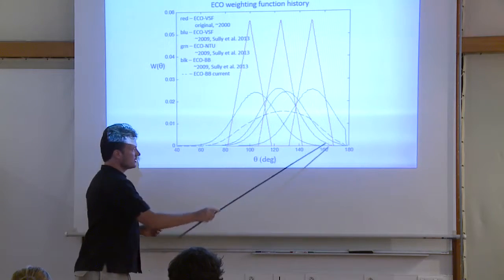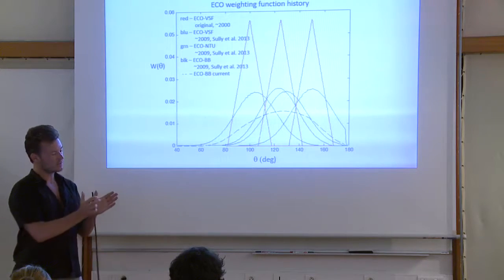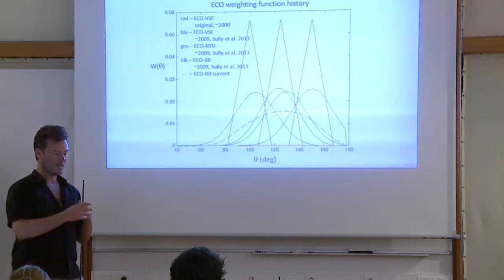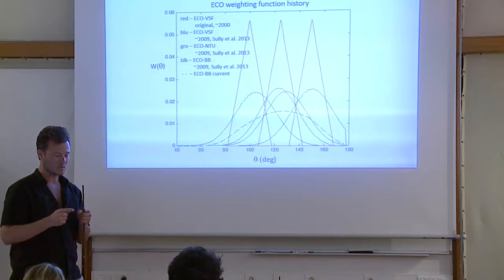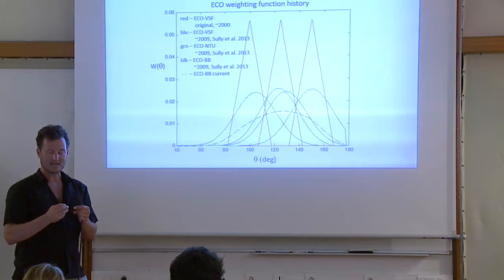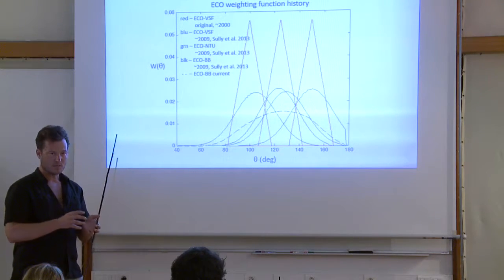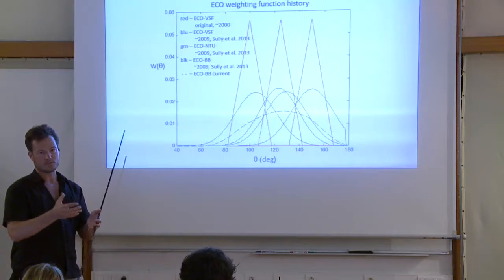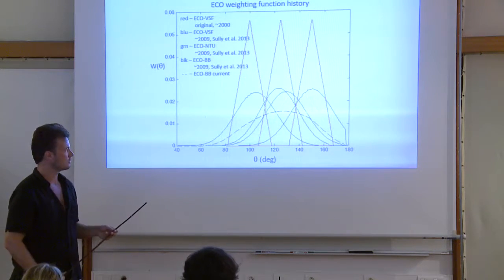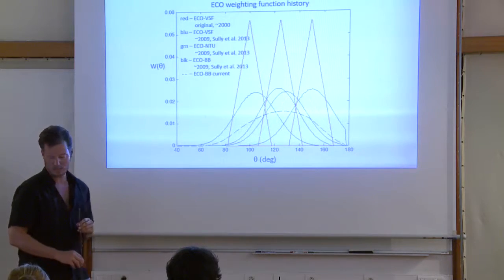You know, having a broad weighting function, there was a lot of logic behind that in the original design of the Eco. So you notice the source beam and the detector beams are very, very broad. That's because we wanted as big a sample volume as possible while having as close to the sensor face as possible, because you want to minimize the path length that the light has to travel. The farther it is away, I'll talk about that in a minute, but then you have to start worrying about attenuation corrections when that sample volume is far from the sensor face. And with a large sample volume, you're integrating a lot more of the particles in the water. If you have a very, very small sample volume, you start to see a lot of spiking from individual large particles going through the sample volume, so it's important to keep that big. So we want to minimize the path length and make the sample volume as big as possible.